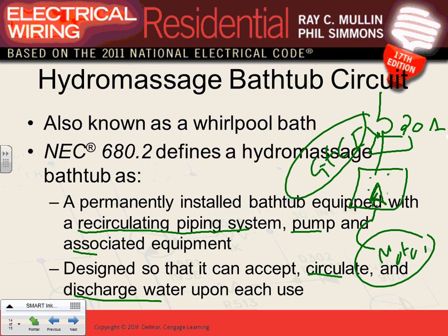So you bring it into the box. Out of the box, you go into the regular receptacle, and if there's any problem, leakage to ground, it will trip, and my wife will walk in here easily, readily accessible, and push the button. Any question, guys, about this hydromassage bathtub? Everybody's okay with that? We don't have it in our bathrooms that we have in the project, but that's how you do it.